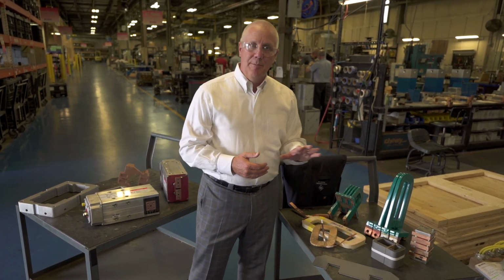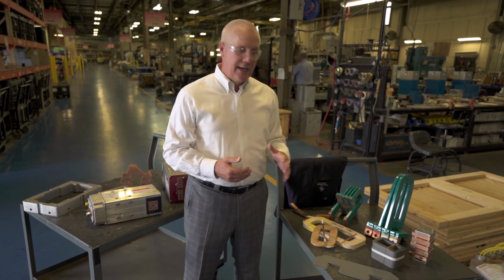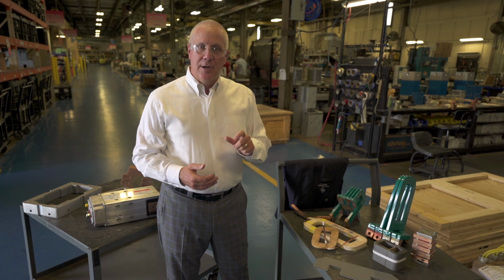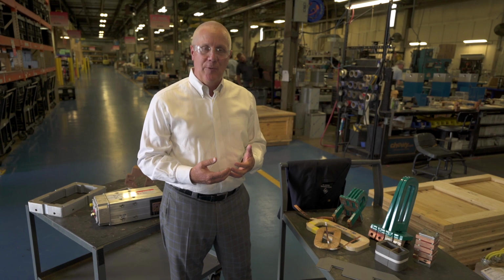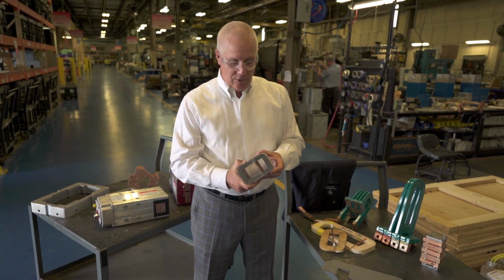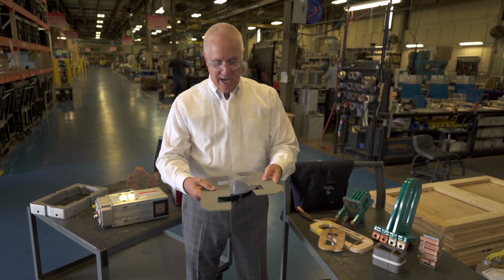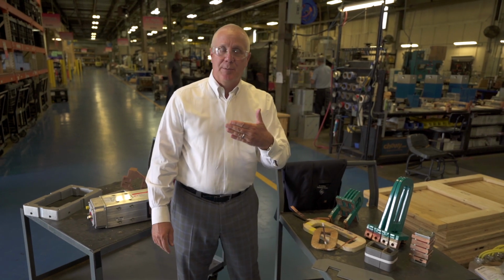It's a fabrication because the unique element of our transformers is that they're water cooled, and the water cooling is carried in the secondary of the transformer. This is the low voltage, high current side of the transformer. The third component that every transformer needs is a magnetic core. For us, it comes in two forms. One is what's called either a wound core or a hypersil core, strips of electrical steel wound into that fashion, or electrical steel stamped into laminations. Looks like this.